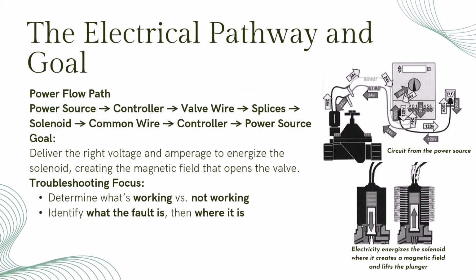Every irrigation electrical circuit follows the same path, from the power source through the controller, out to the valve and solenoid, and back again. The ultimate goal is to deliver enough voltage and current to energize the solenoid. When it is working correctly, that magnetic field lifts the plunger, the diaphragm opens, and water flows. If that doesn't happen, our job is to find out what in that path failed and where it happened. Troubleshooting starts at the controller because if there's no power there, nothing downstream will work. Once the controller checks out, we move to the valve circuit.